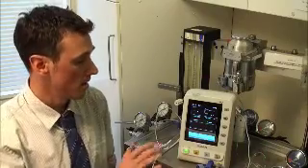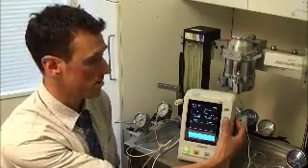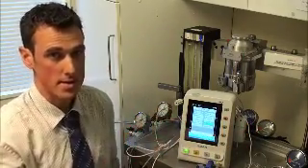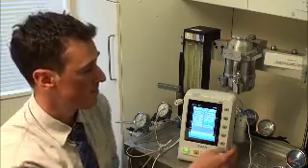In theatre, when you first switch on the machine, if you select the menu button, you can input information such as patient data, etc. It's unlikely that you would do this for each patient, but the option is there if you would like to. What you must do, however, is check the alarm setup and the carbon dioxide levels.